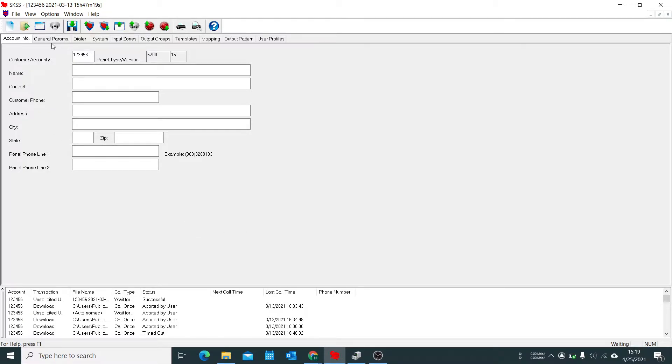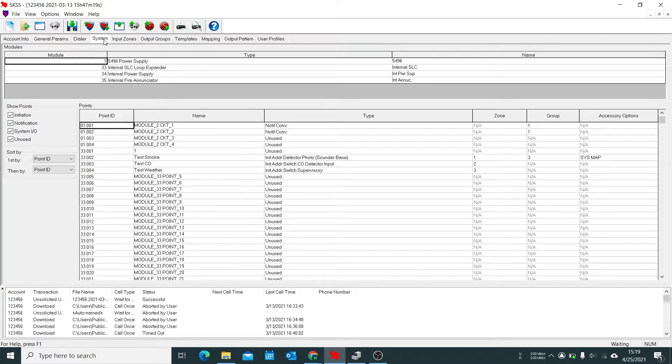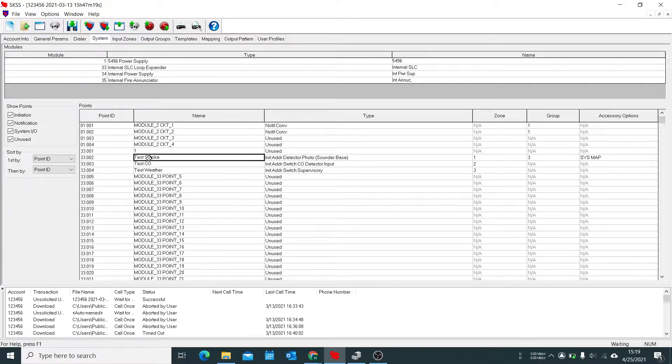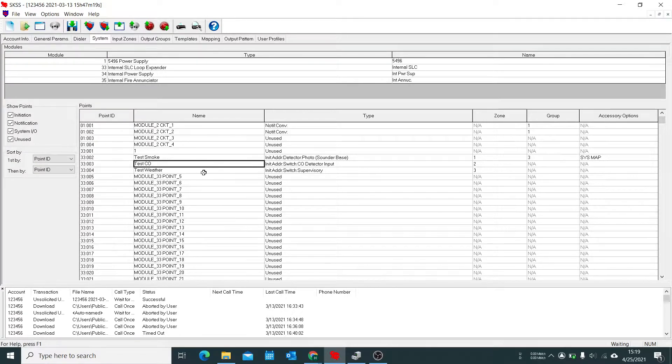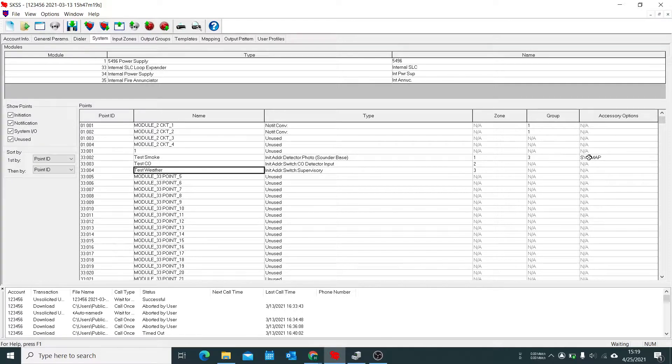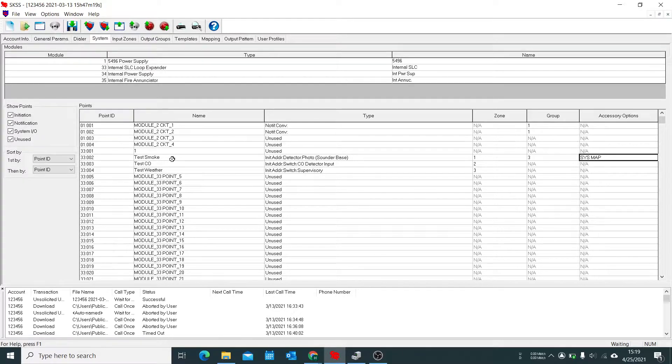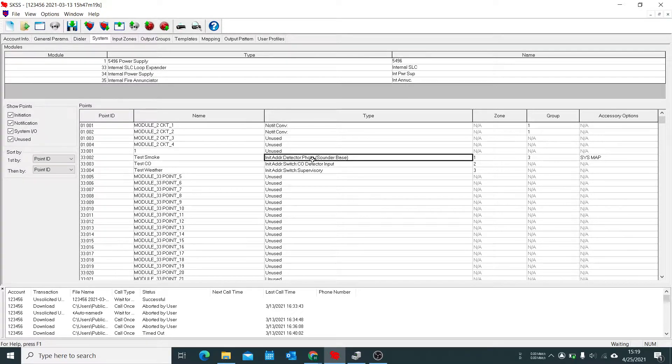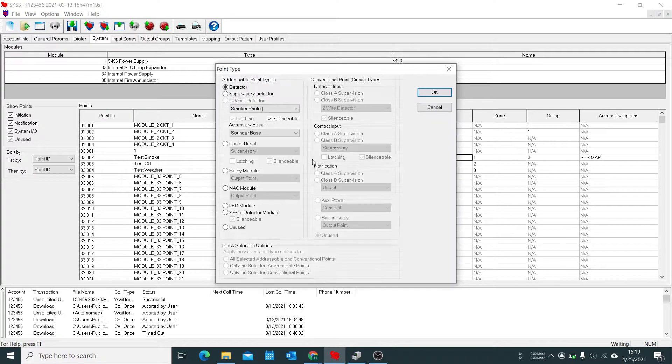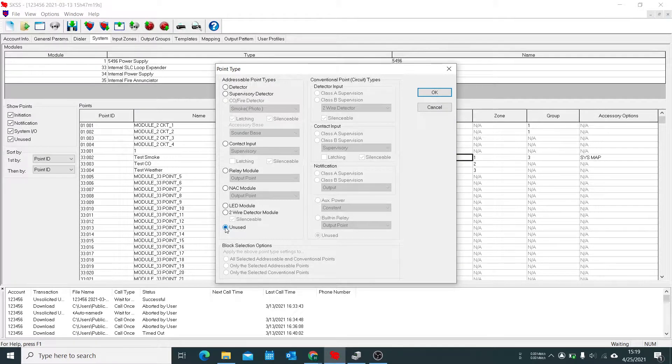So we have my panel open right now. First we're going to go to our system and we're going to add our devices. So right now I have a test smoke detector, test CO which will be a monitor module, and then a weather supervisory. So the way this works is let's go to that smoke detector which is connected to the sounder base. Open up its settings.